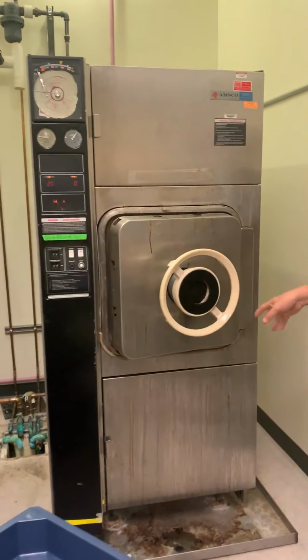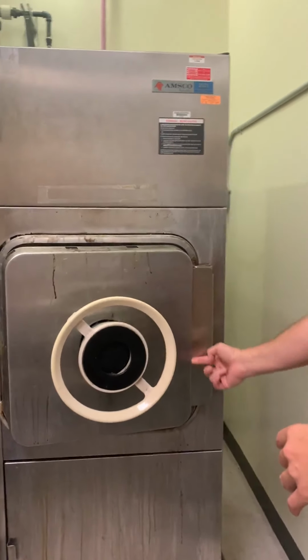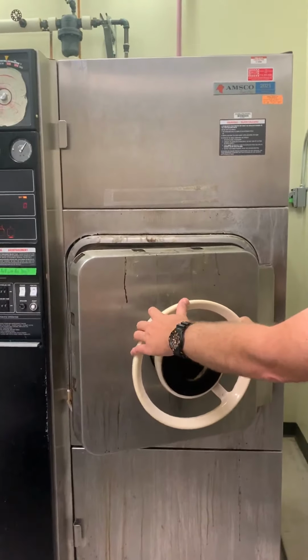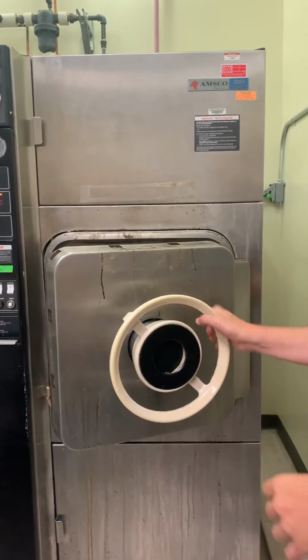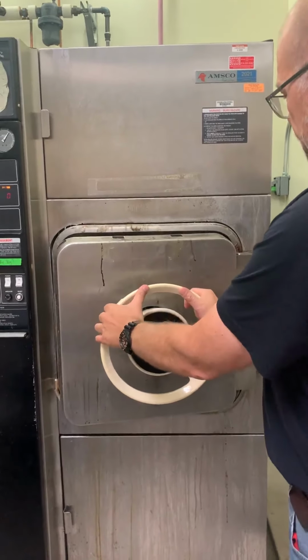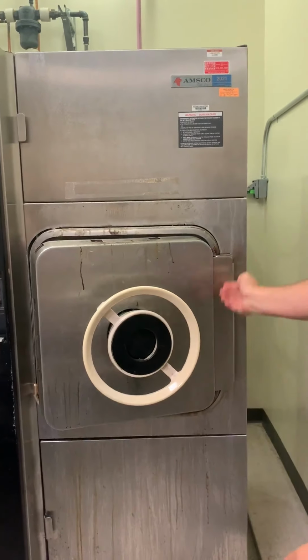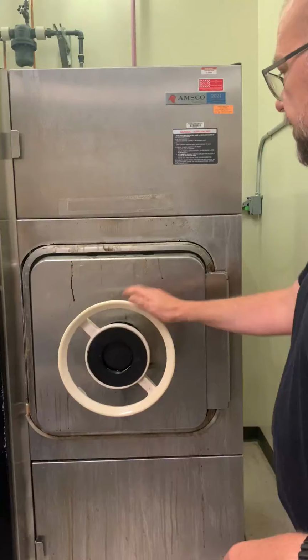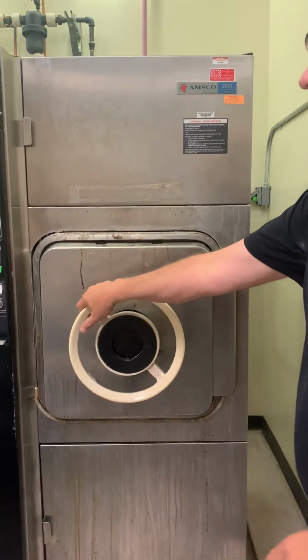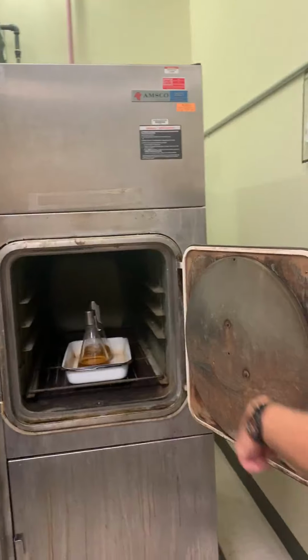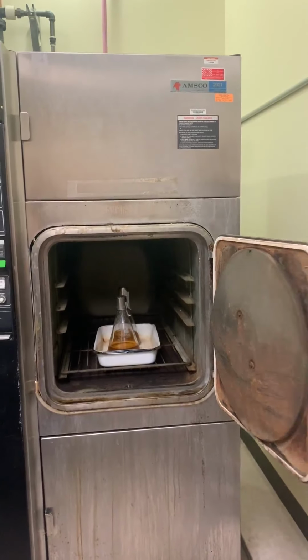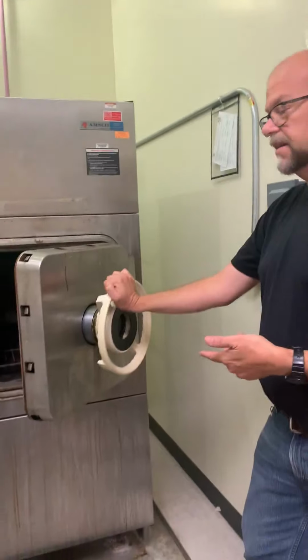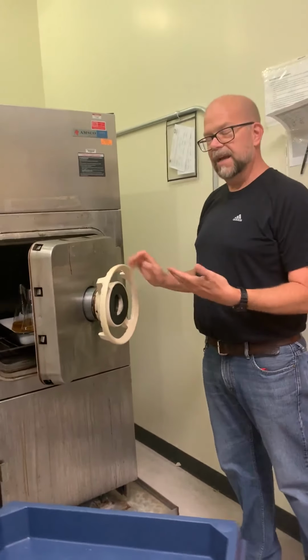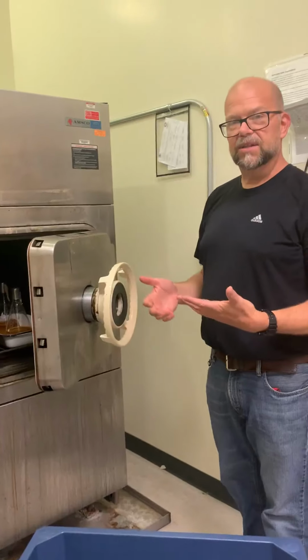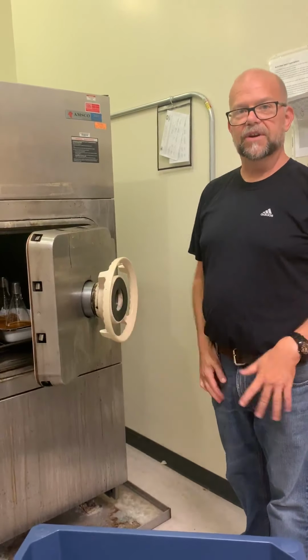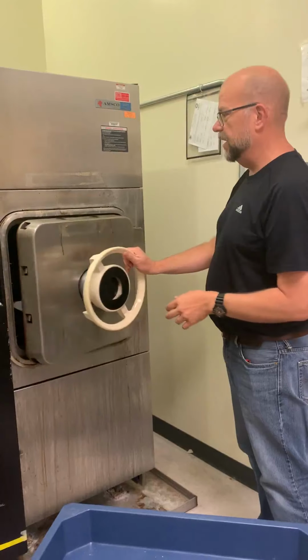Right. This door hinges in 2 places. One right here and one inside the door. So it'll allow you to move the door like that. It's important when we're closing this door that we cant it all the way to the right, towards the hinges. So when we shut it, this gasket is making contact all the way around. Right? There's the gasket. You can see where it sits and seals. This door will allow you to close it without that gasket being sealed completely. And that just creates a mess once you start the cycle. You're going to have to abort it and start it over again. Right? So we make sure that it's canted all the way to the right.